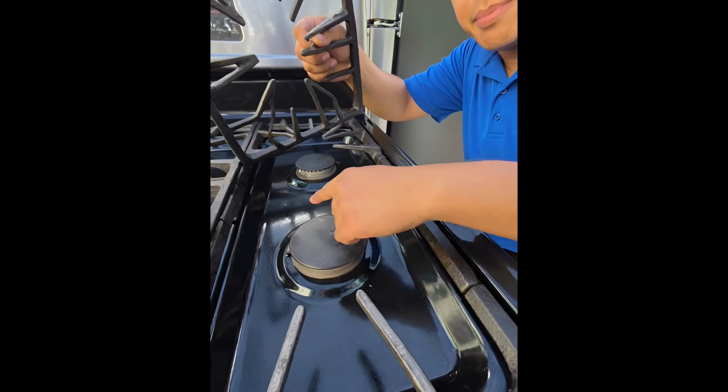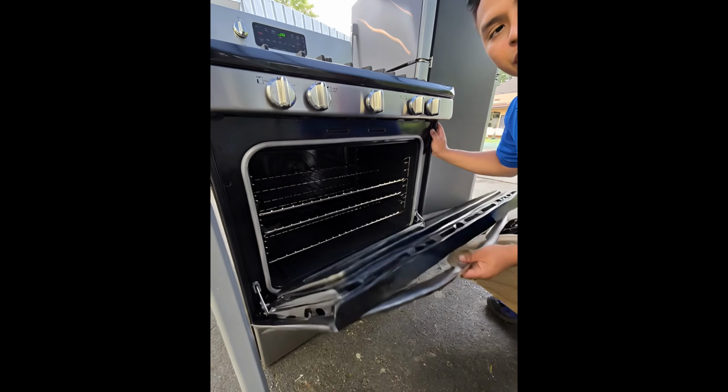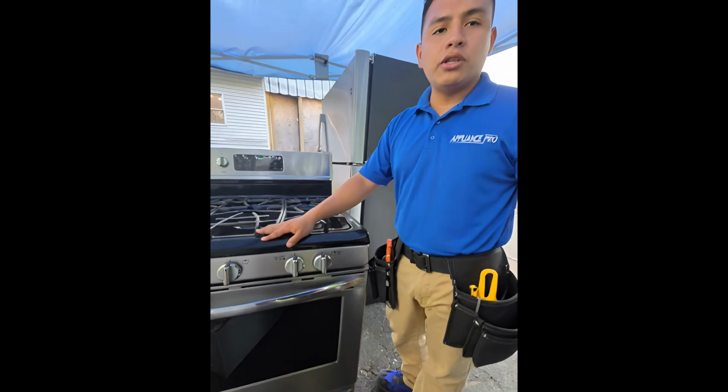Here, we start checking the temperature sensor since if this component sends incorrect readings, the system cannot regulate heat properly. In the workshop, we explained that the oven completely depends on this information to function correctly, and when there are inconsistencies, the board interprets that something is wrong and triggers F13 as a safety measure.